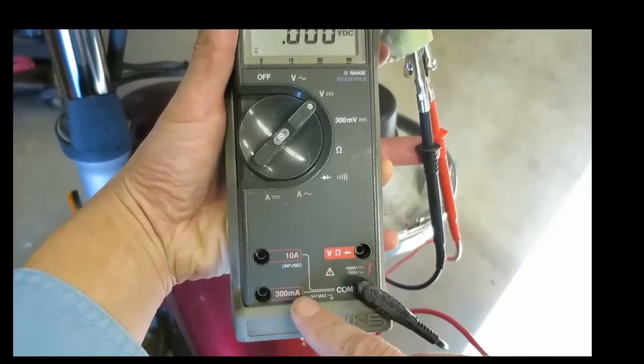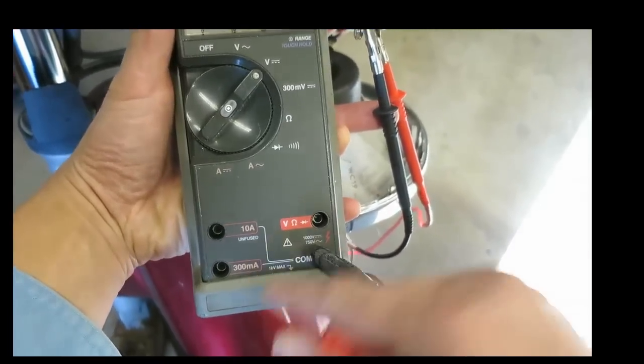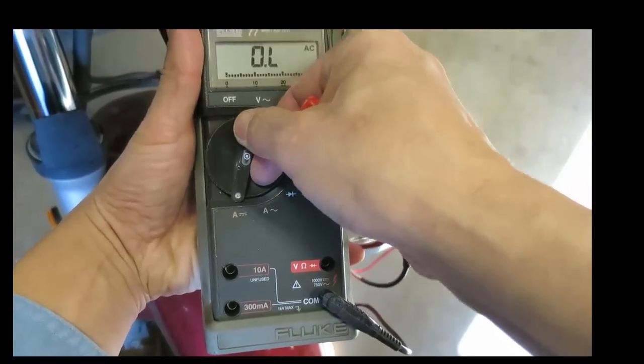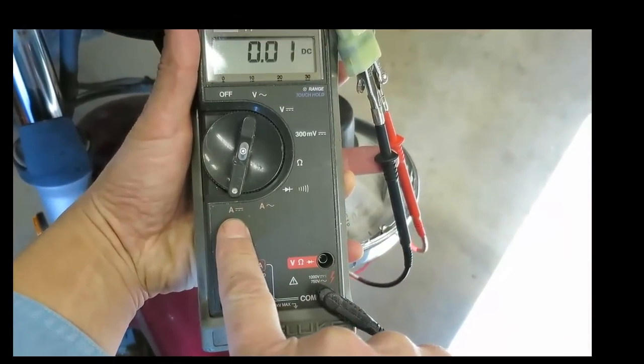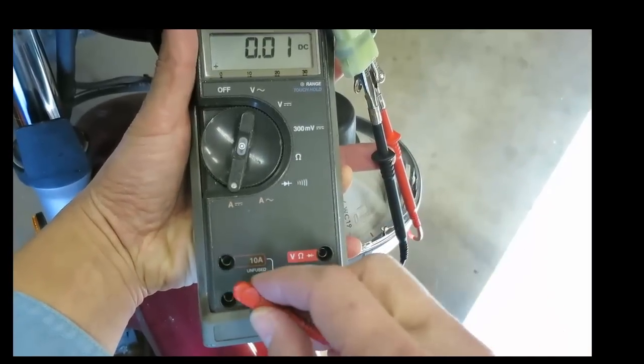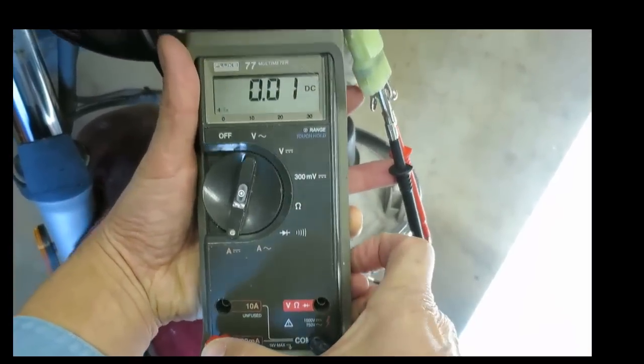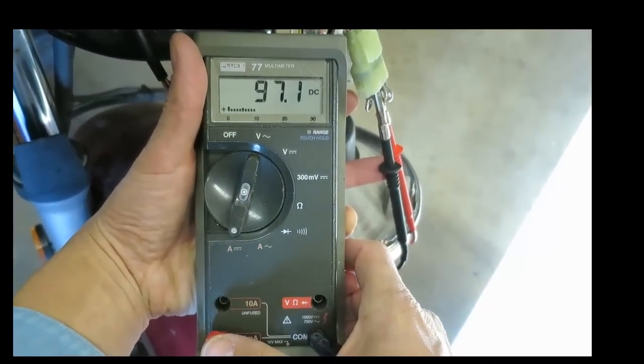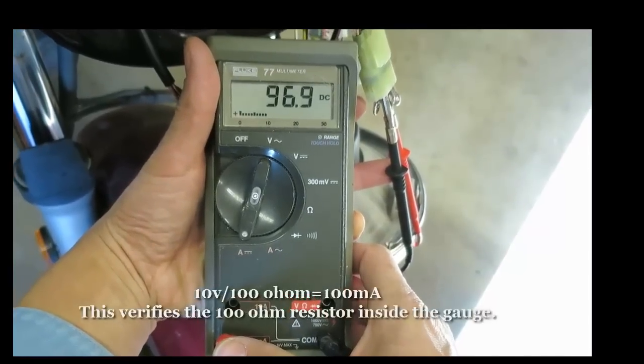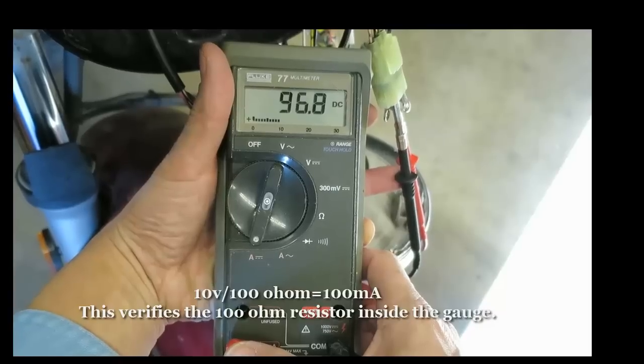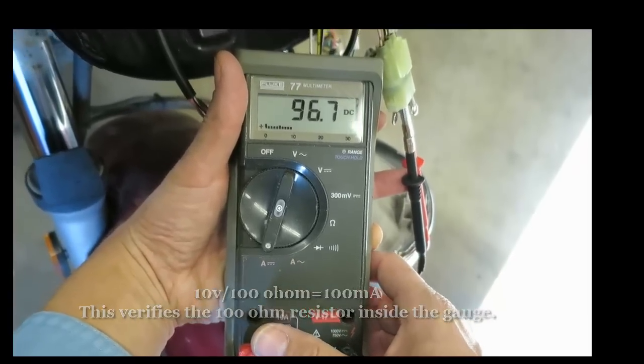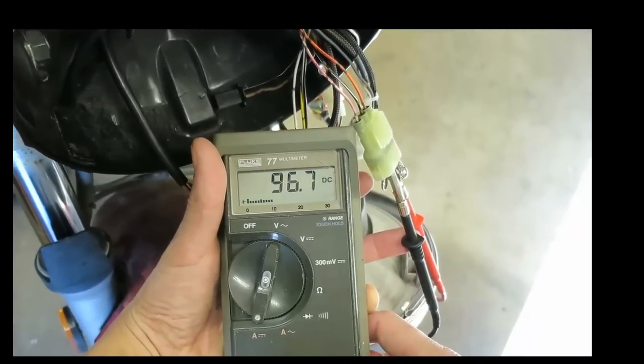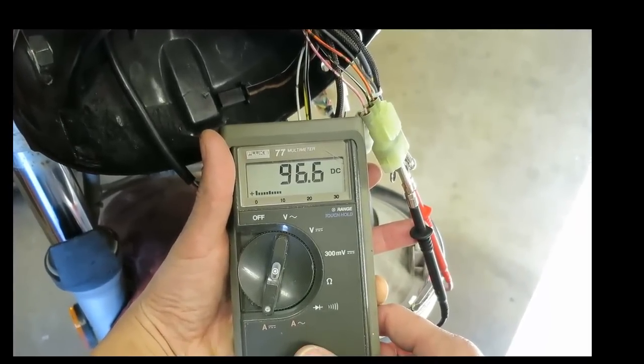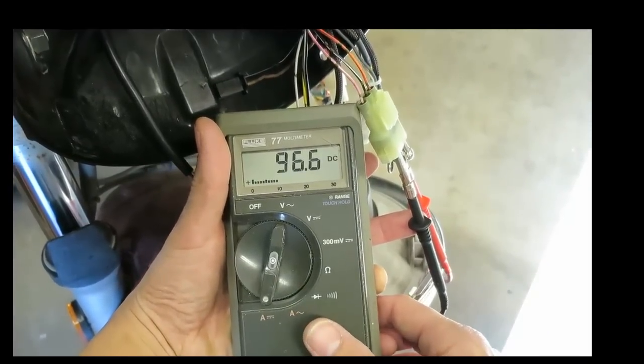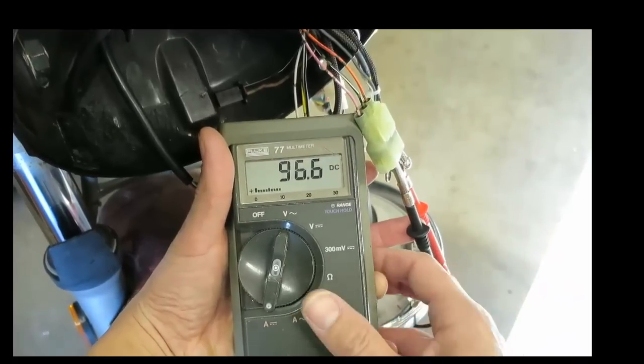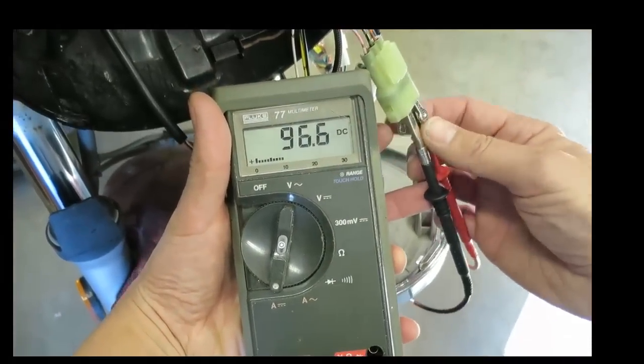You can plug it into a 10 amp port or a 300 milliamp port. We're going to use the 300 milliamp port. Turn the meter setting to DC amp, plug it in, and we should see about 100 milliamps, so 97. That's because the voltage inside the gauge is about 10 volts, and we have a 100 ohm limit resistor in there, and 10 divided by 100 gives us the 100 milliamps. So that proves that the power from the gauge is okay.